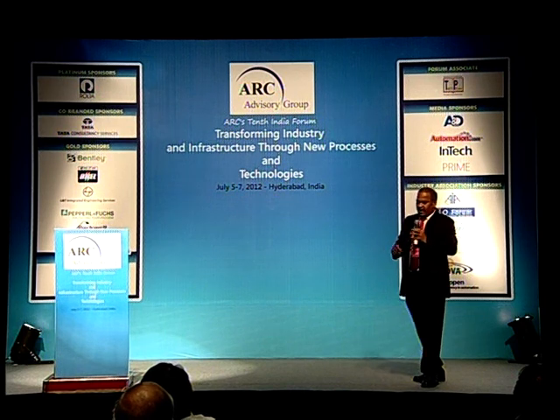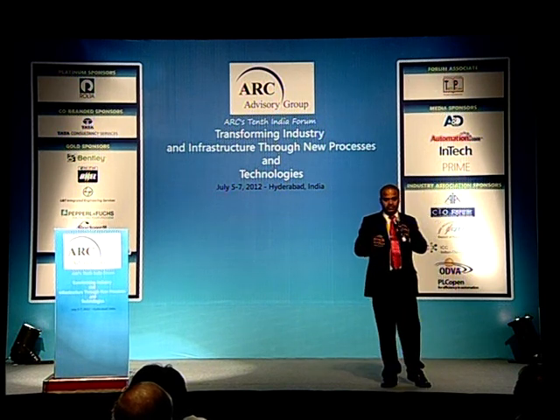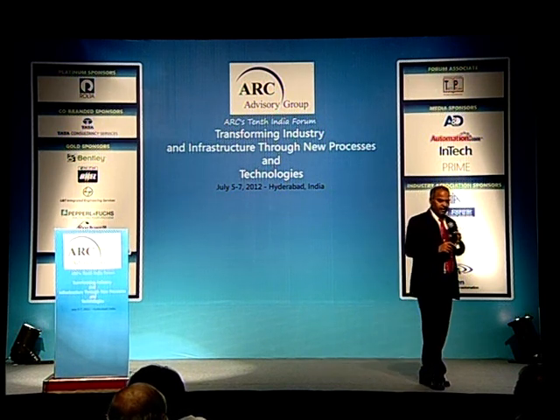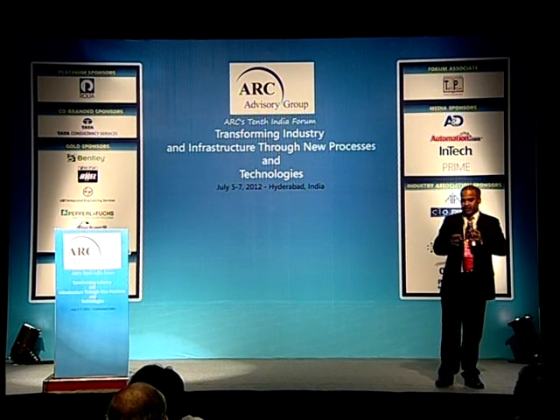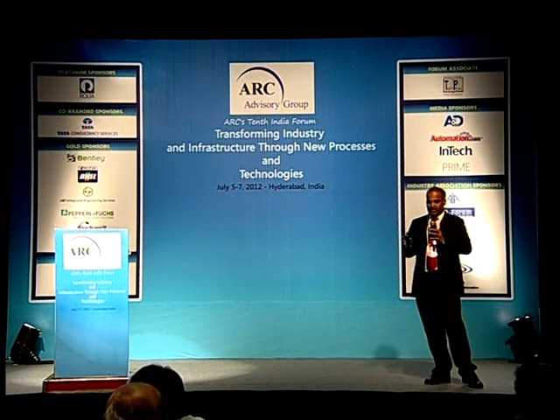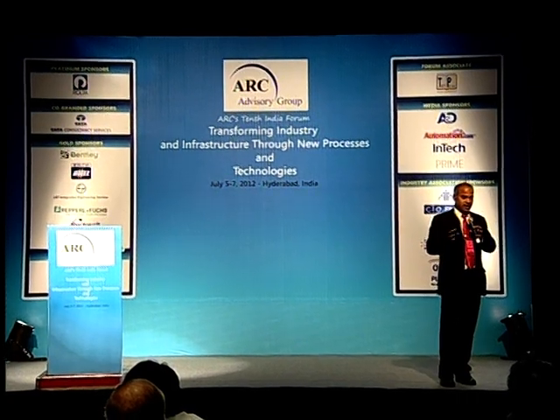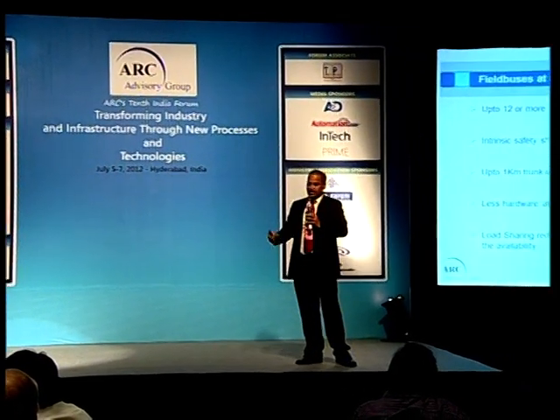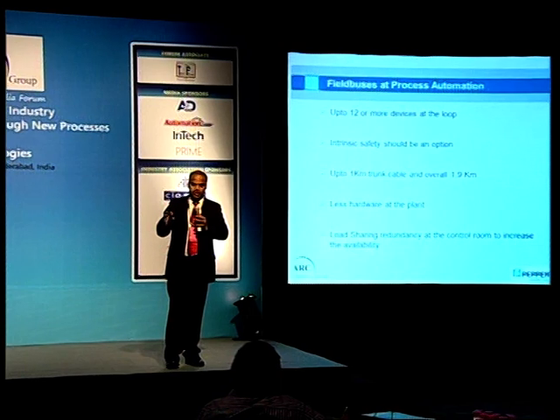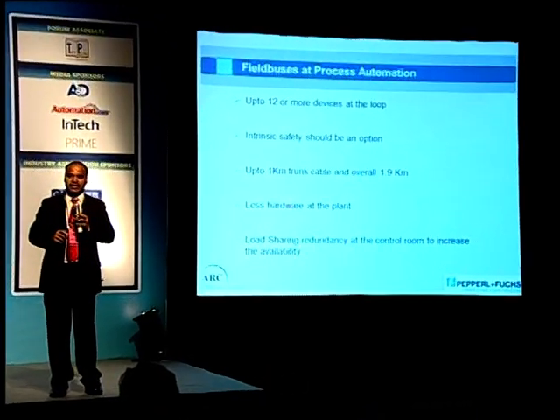And also we prefer to have less hardware at the plant. Being a digital plant, we also try to minimize the number of hardware. And of course, we also want to have some other features like redundancy at the control room, at the power supply and the DCS level, etc. But applying intrinsic safety in this situation is going to have some limitations.